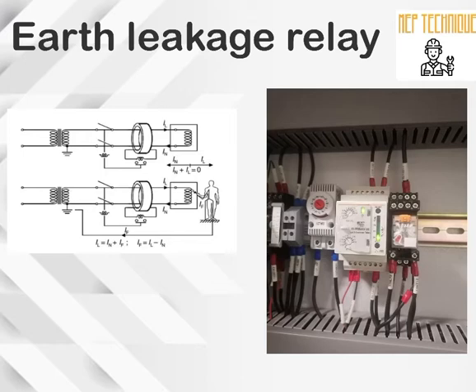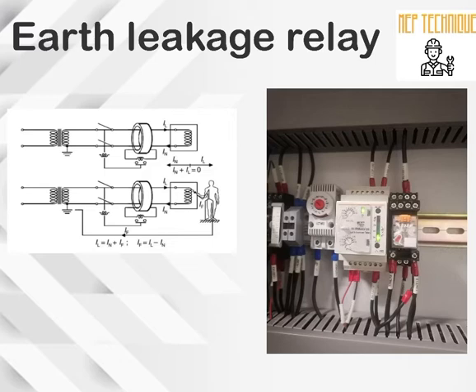The ELR consists of a core balance CT mounted at the source end. Any time a human comes in contact with any part of the line, a portion of the current will flow through the body. This will result in an imbalance in the current entering and returning to the CBCT of the ELR. When the fault current flows through the human body, the relay is triggered by the unbalanced quantity and the ELR is immediately tripped. That is how an ELR works.